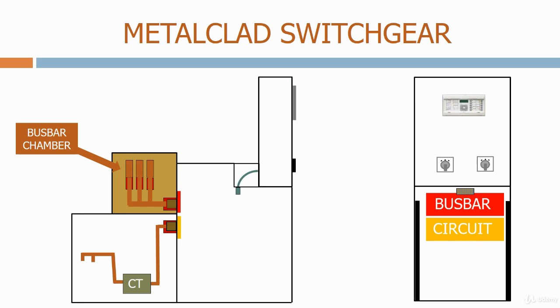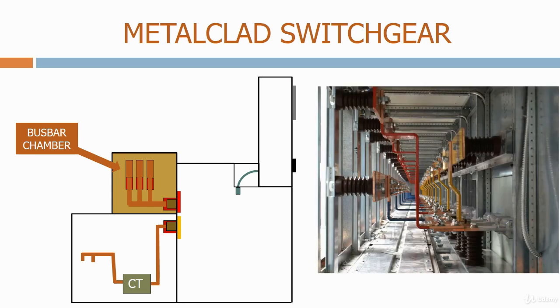Next, we have the busbar chamber. This contains all of the bus bars that connect all of the incomer and feeder circuits together. Here's a typical example. The bus bars are mounted on epoxy insulators to keep them away from the grounded enclosure.